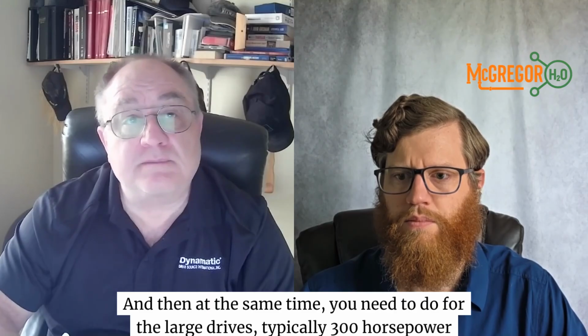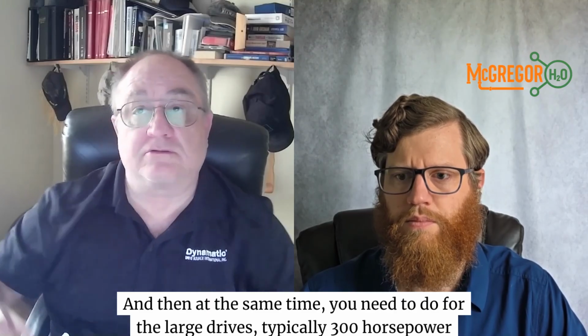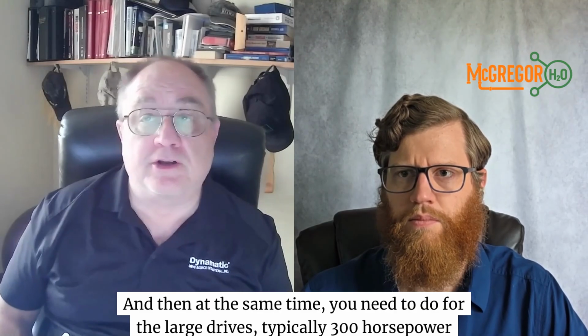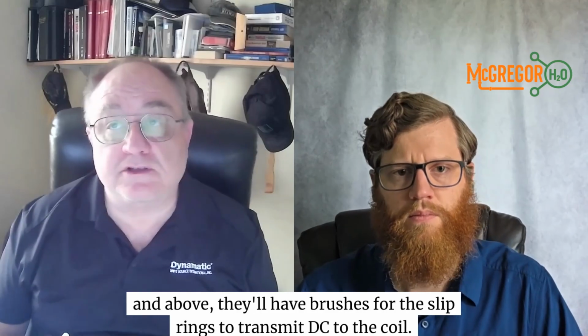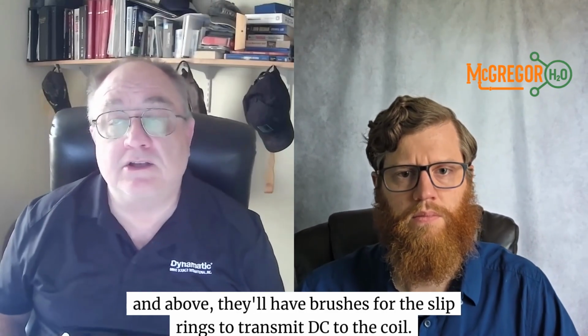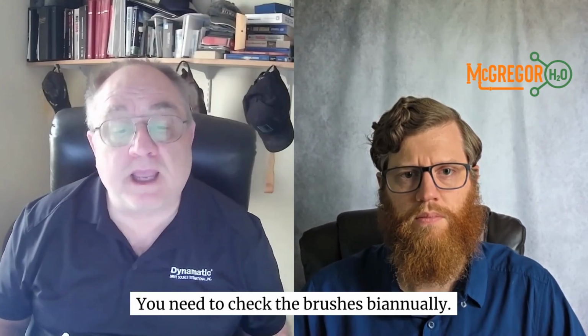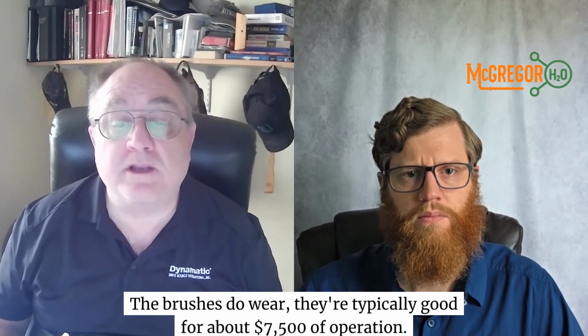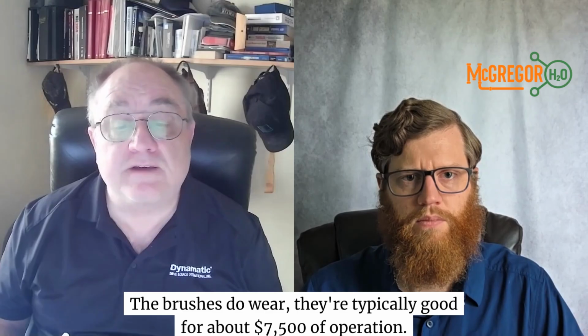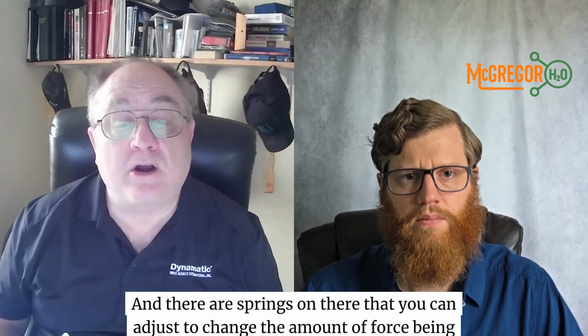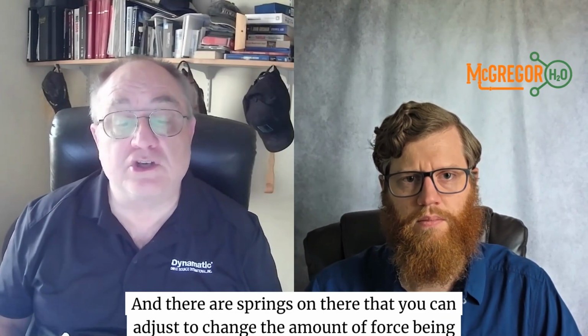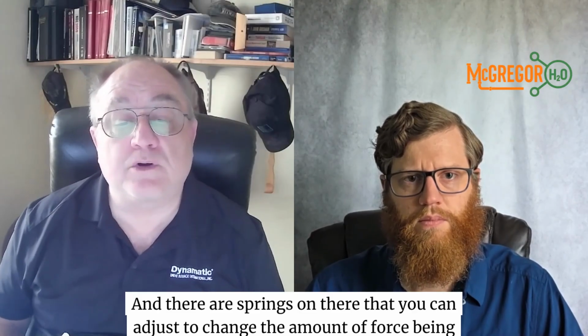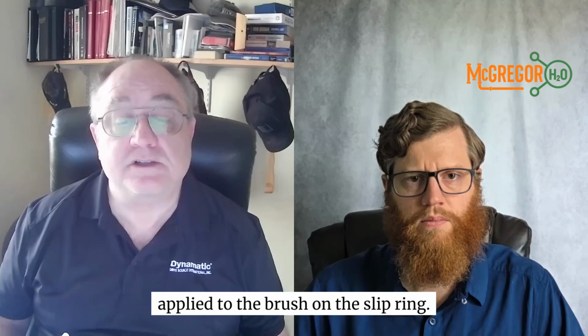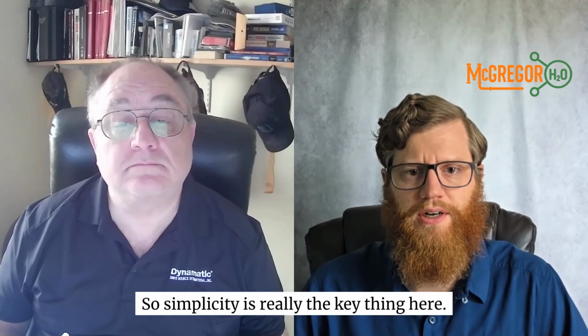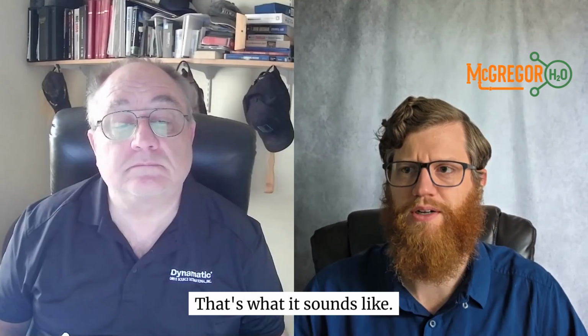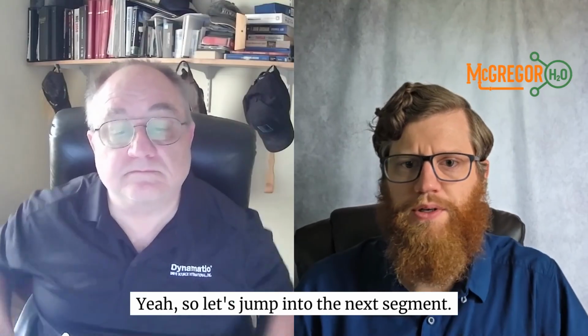And then at the same time, for the large drives, typically 300 horsepower and above, they'll have brushes for the slip rings to transmit DC to the coil. You need to check the brushes biannually. The brushes do wear. They're typically good for about 7,500 hours of operation, and there are springs on there that you can adjust to change the amount of force being applied to the brush on the slip ring. So simplicity is really the key thing here. That's what it sounds like. Pretty much. Yeah, so let's jump into the next segment.